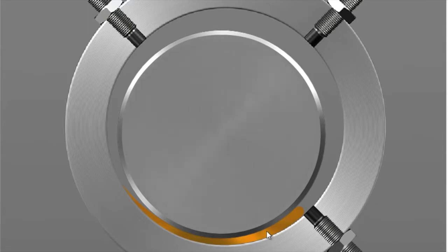But unfortunately, if we've got some unbalance or whatever is causing the shaft to move, that vibration doesn't transmit well through the oil out to the bearing, and so therefore an accelerometer may not pick up what's going on. So we use these proximity probes instead.